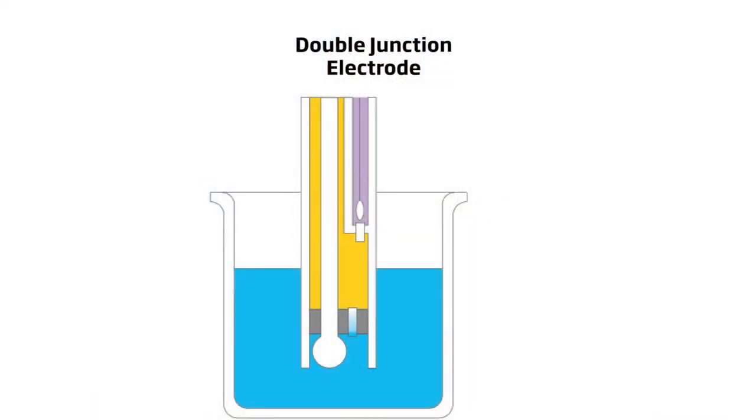In double junction electrodes, there are two separate chambers, one of which contains silver chloride and the other that does not.